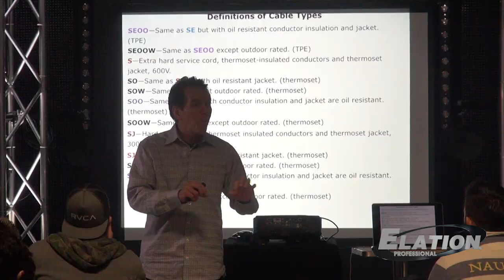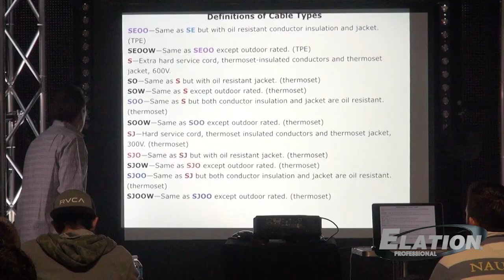So type SJ in our world is okay for power cables like this, up to 3 feet long. It's good for breakouts, it's good for twofers, but it's not supposed to be used for any other applications in our industry. That's type SJ. It's good up to 300 volts. So if you try to use type SJ cable with a 480 volt circuit, that's a problem.